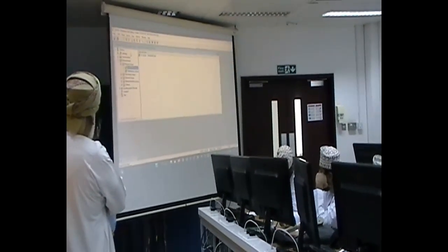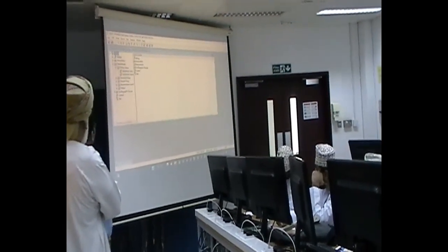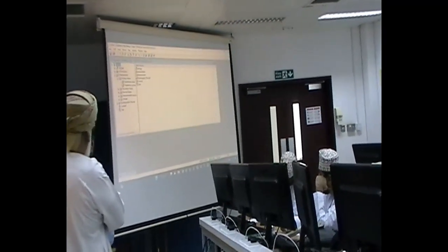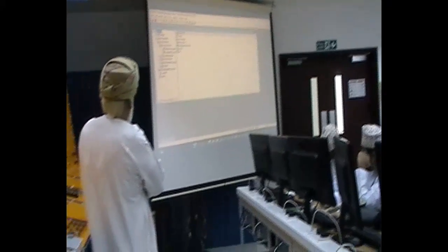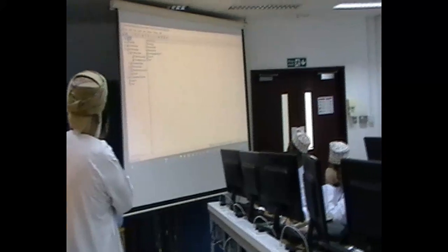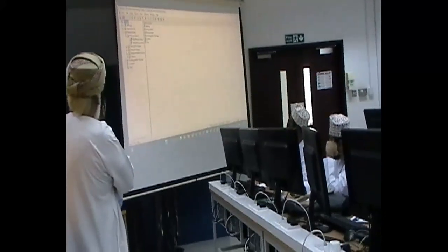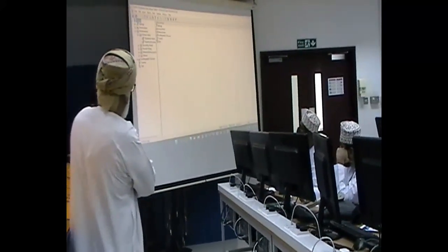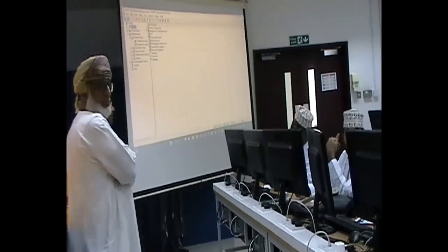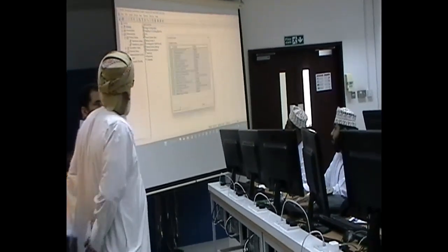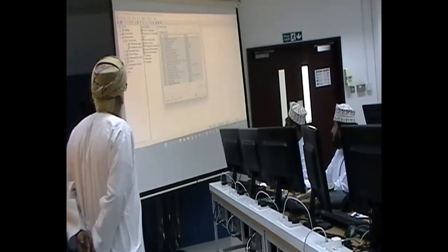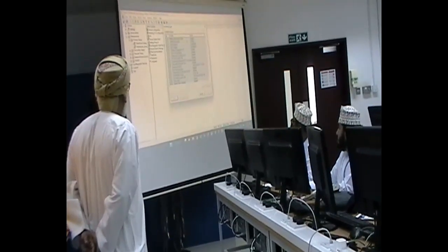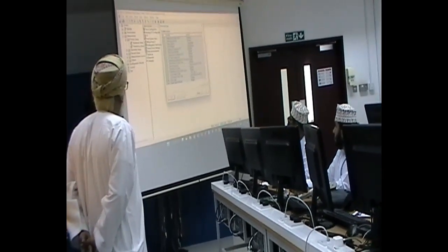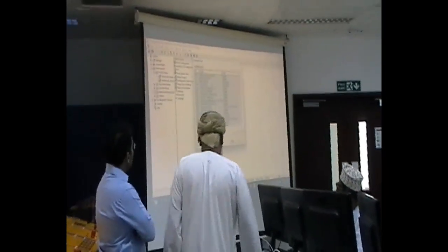This is the setting. First of all, this is online, so I'm already communicating with the relay. I hope it's clear, and I cannot see the communication, but here at least we can see this is online now. I'm communicating with the relay, and I have the setting. I have device configuration where I can enable or disable any function of the relay. For example, I have differential protection enabled. I have distance, or we call it phase distance.